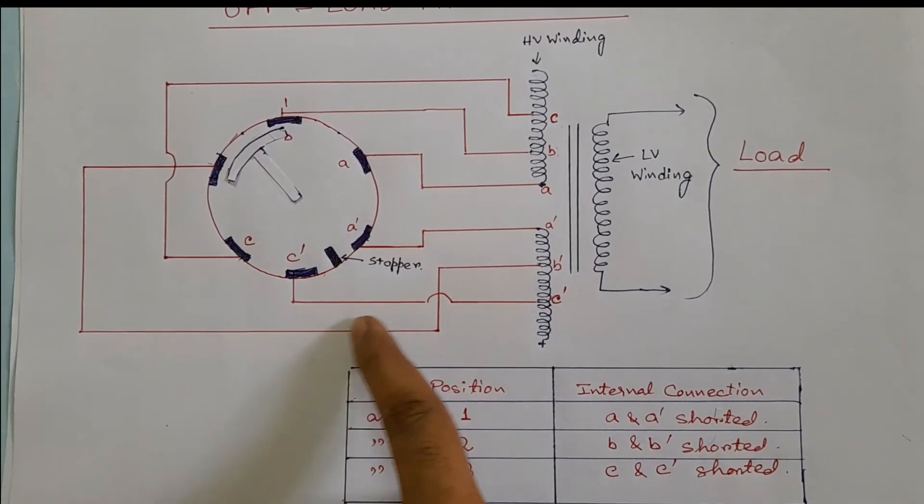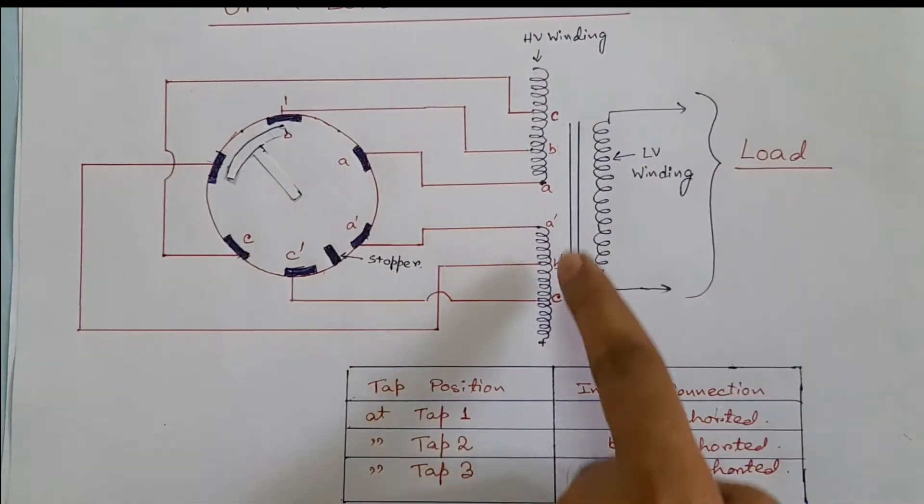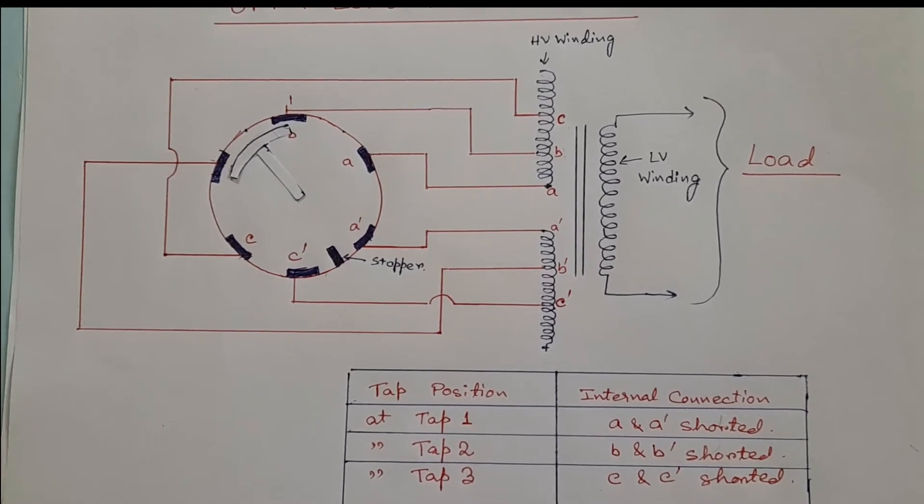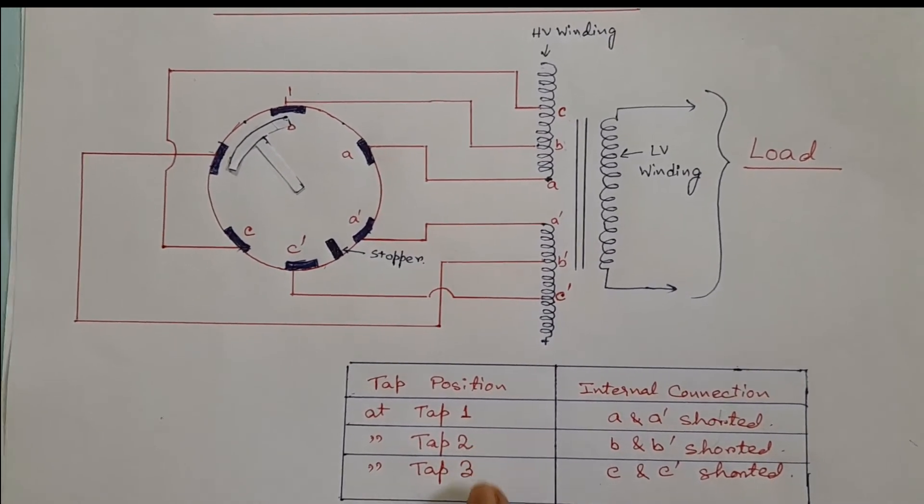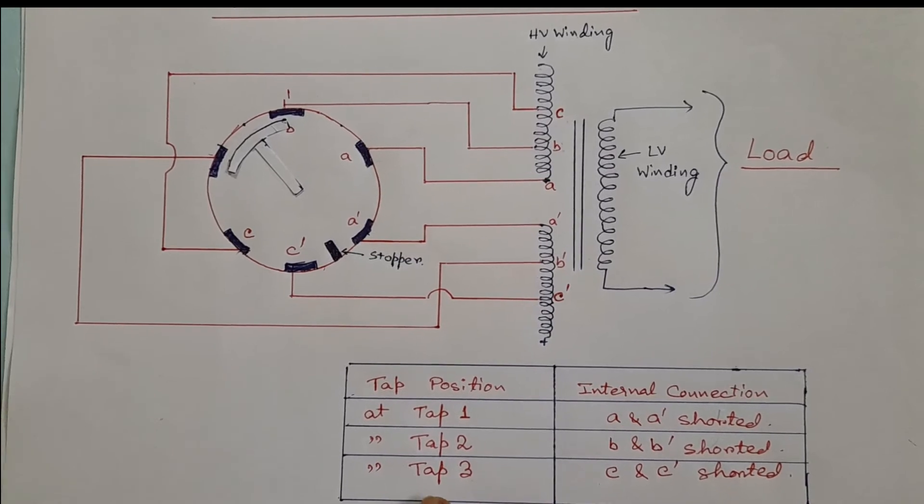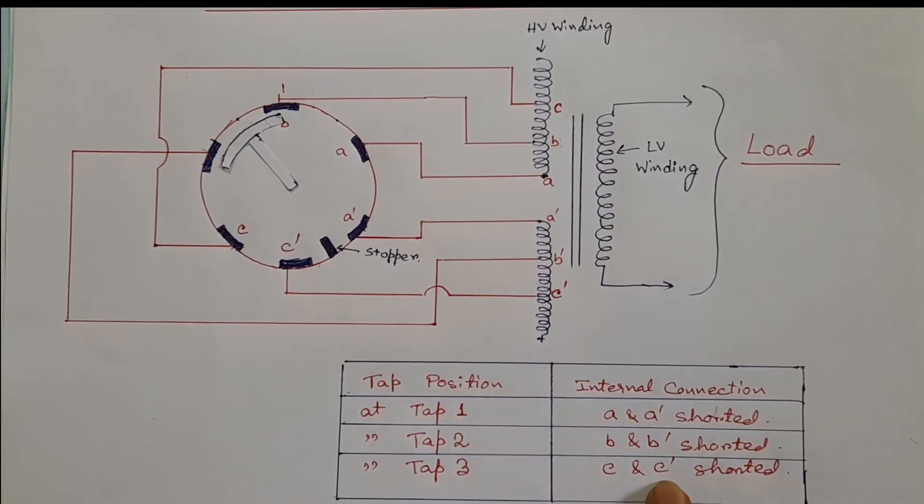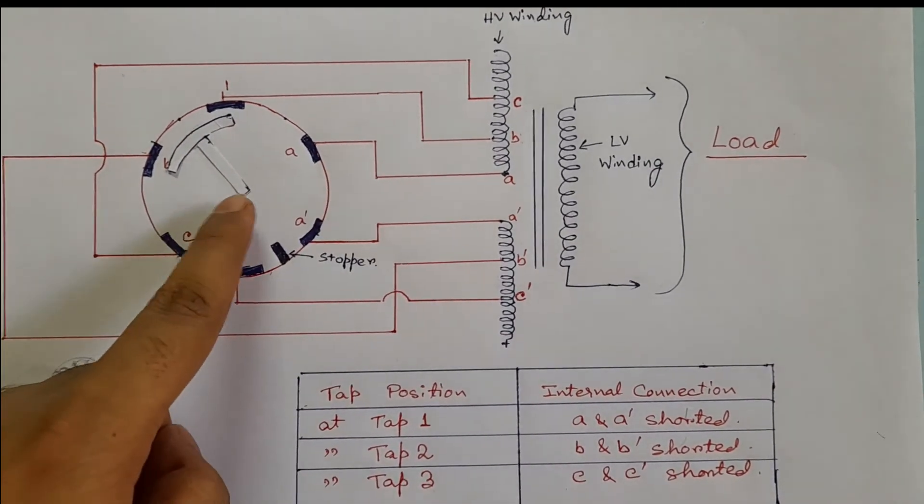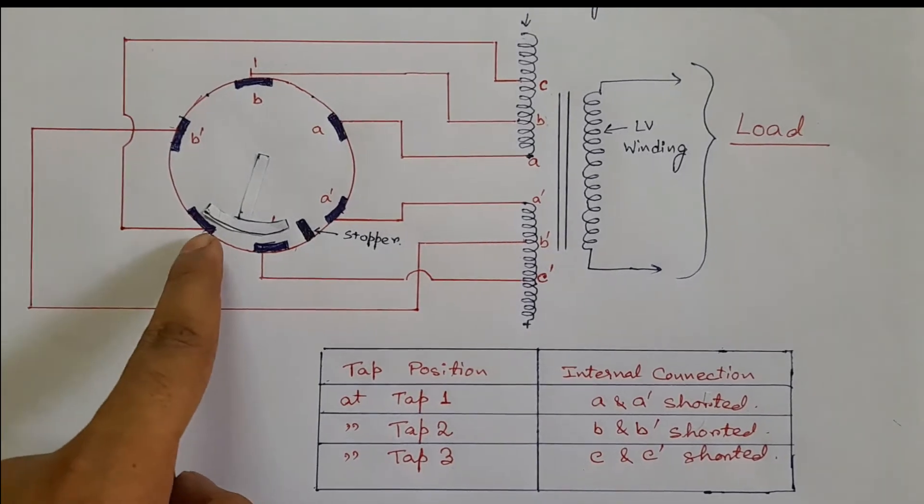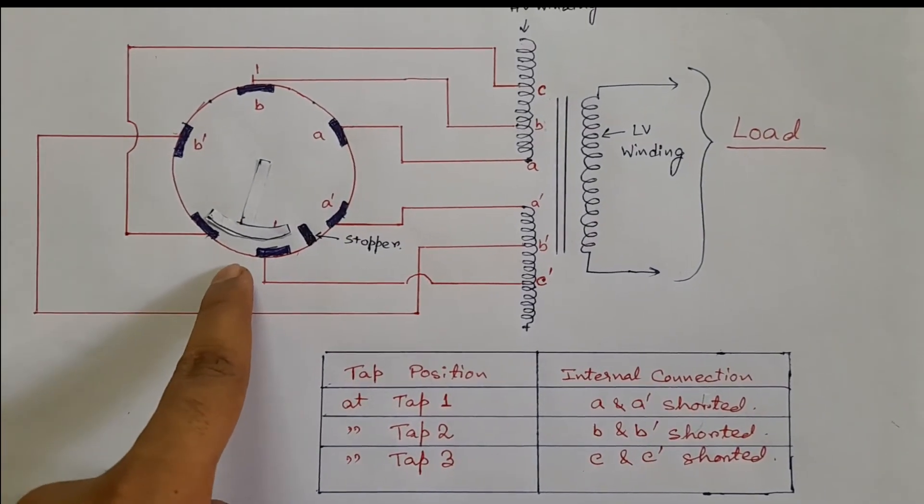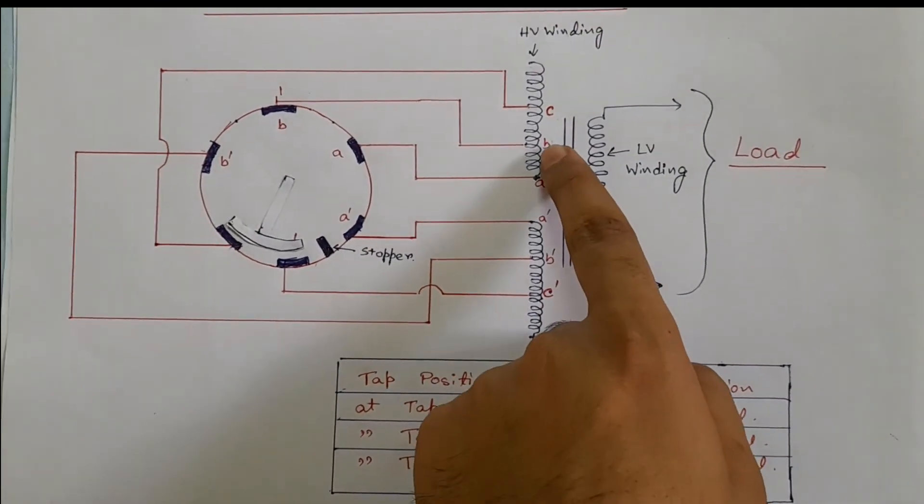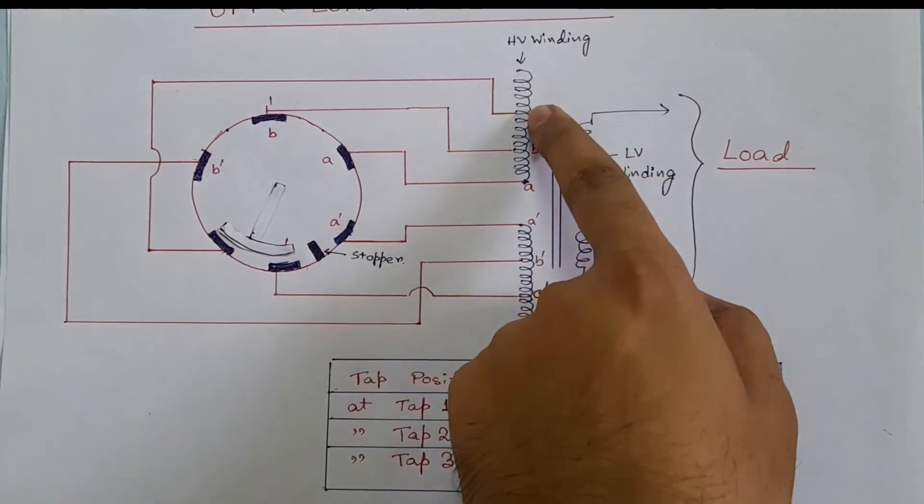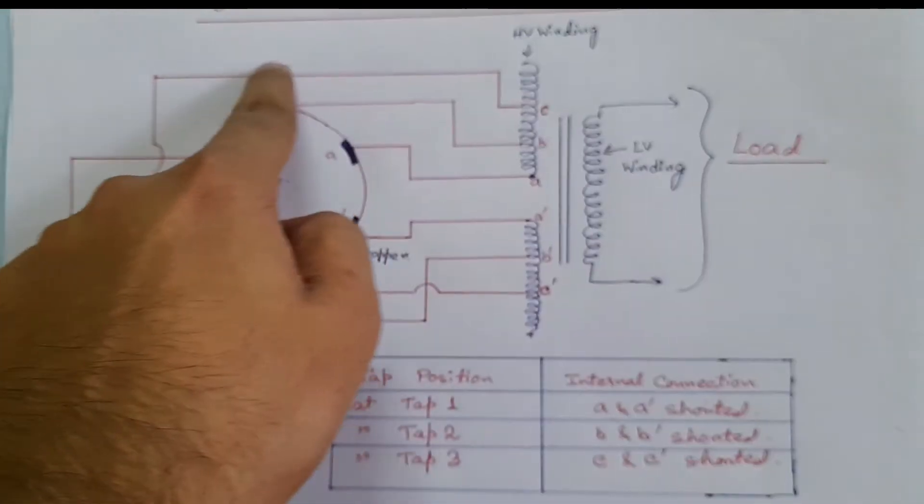So a path is established and upper and lower windings are connected. Similarly, if we want to change tap position from two to three, then at tap position three, C and C' should be shorted. So this rotary switch will rotate and short C and C' terminals. A connection between upper and lower winding is again established and now the HV current will flow through this path.